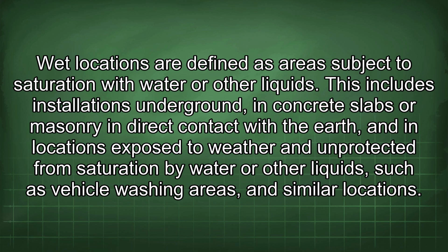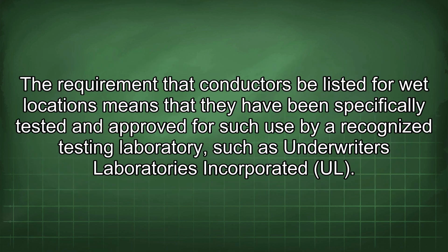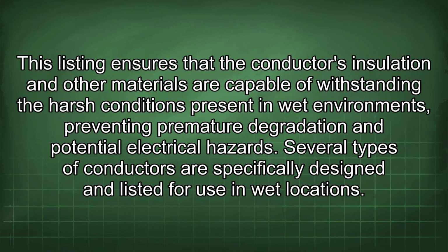This includes installations underground, in concrete slabs or masonry in direct contact with the earth, and in locations exposed to weather and unprotected from saturation by water or other liquids such as vehicle washing areas and similar locations. The requirement that conductors be listed for wet locations means that they have been specifically tested and approved for such use by a recognized testing laboratory, such as Underwriters Laboratories Incorporated, UL. This listing ensures that the conductor's insulation and other materials are capable of withstanding the harsh conditions present in wet environments, preventing premature degradation and potential electrical hazard.